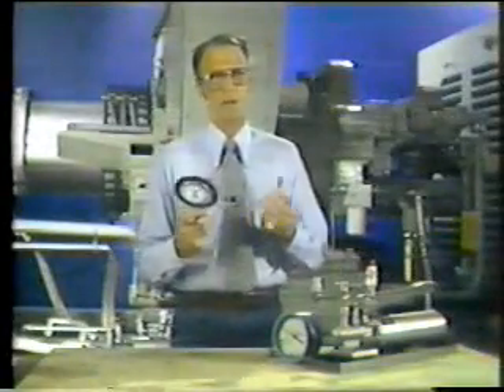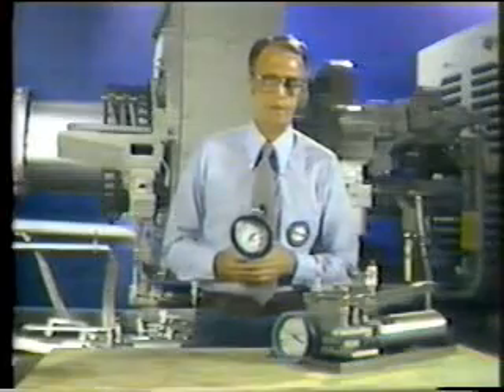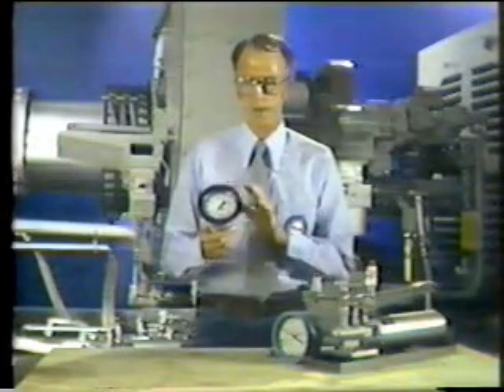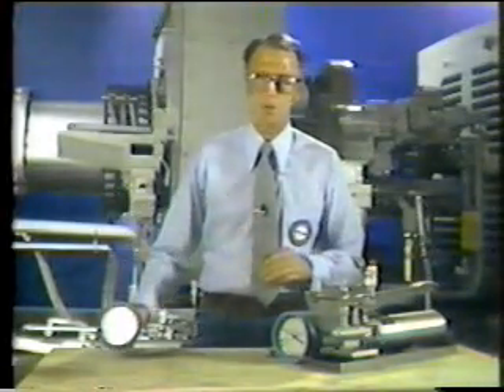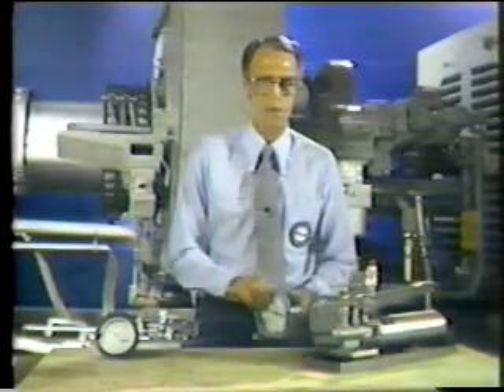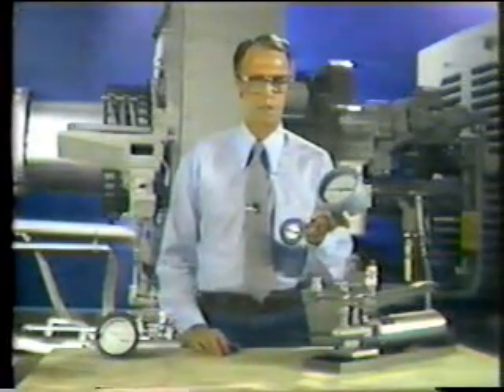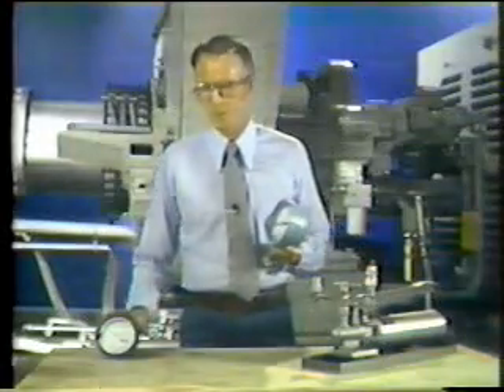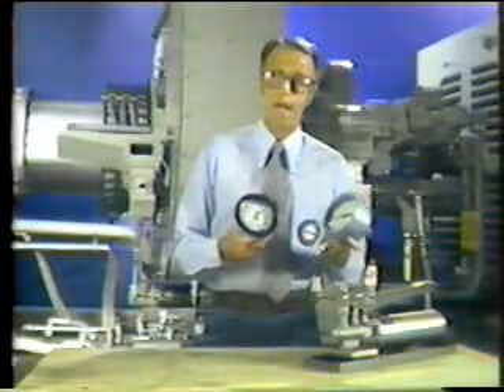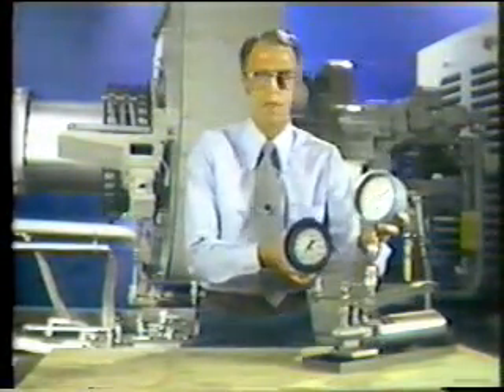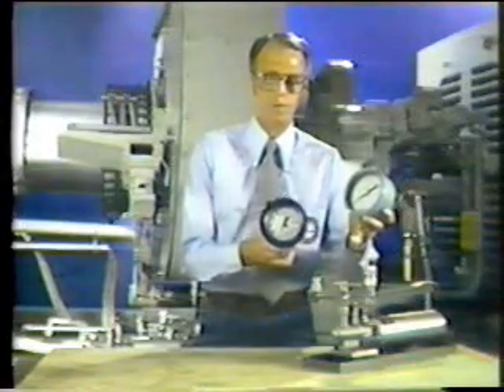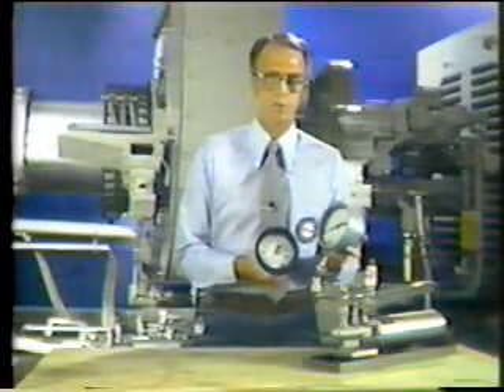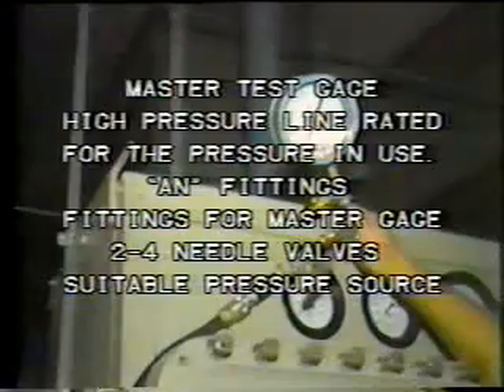Calibration of a gauge can be accomplished using several different methods. In the comparison method, the gauge can remain in the control panel and be calibrated using a master test gauge. Another method is to remove the gauge from the panel and calibrate it using a dead weight tester. In the following procedure, you will calibrate a gauge using the comparison method.